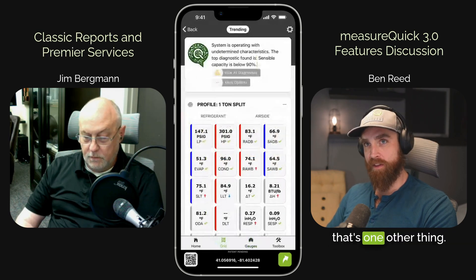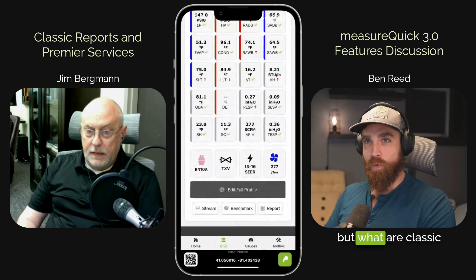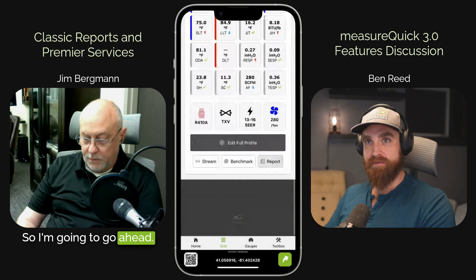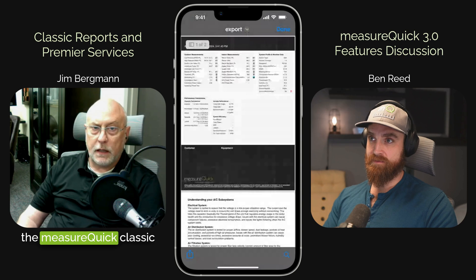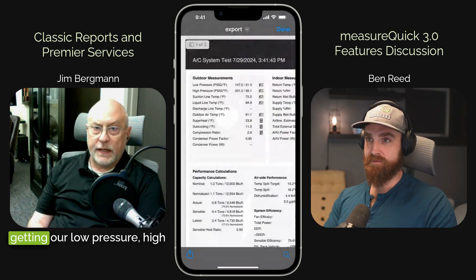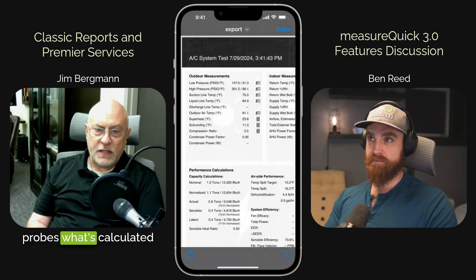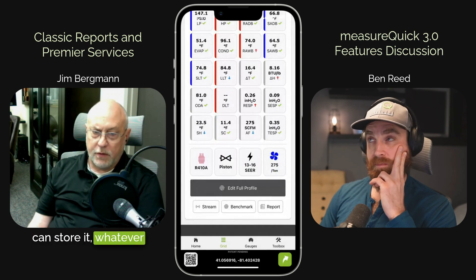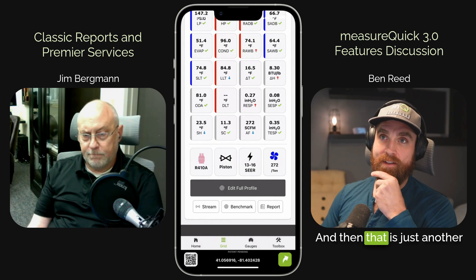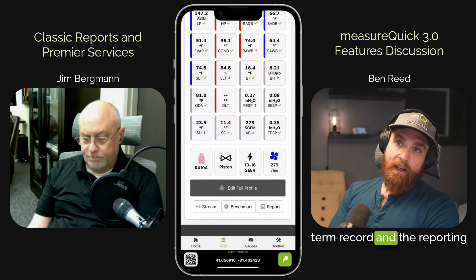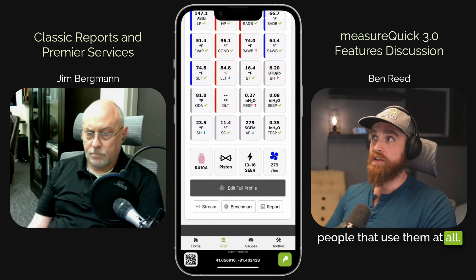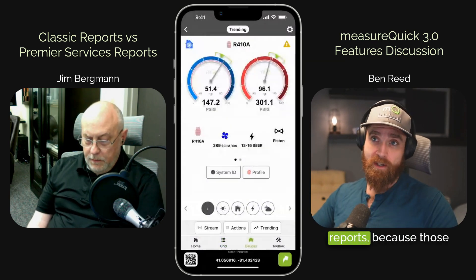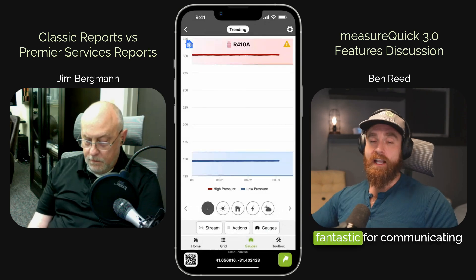Now, classic reports — that's one other thing that's included in this update. So I'm going to hit report here and that'll generate the MeasureQuick classic report. The MeasureQuick classic report is just all the readings off the system — in this case we're getting our low pressure, high pressure readings, suction line temp. These are all coming off JB probes. It's what's calculated, what's measured, all the readings. The basic reporting allows you to email it, store it, whatever you want to do — it pulls in all the measurements from the project you're in. And that is just another version of keeping a long-term record. The reporting is one of the coolest features about MeasureQuick, and there's not enough people that use them. Hopefully as you explore these classic report features, that might get you curious about the premier services reports, because those are what get you the vital score, which is absolutely fantastic for communicating value to homeowners.